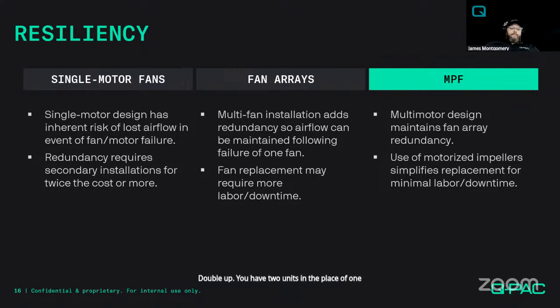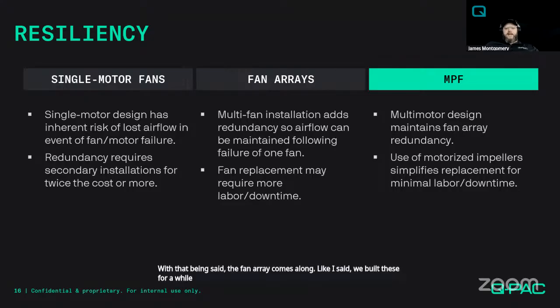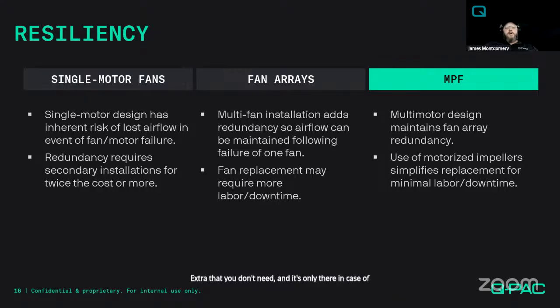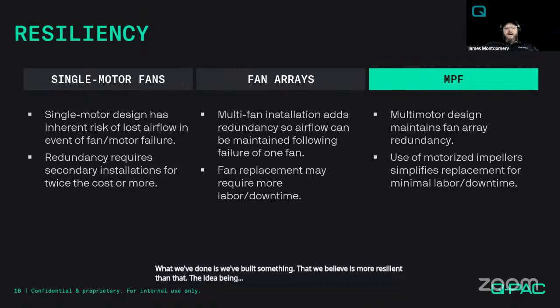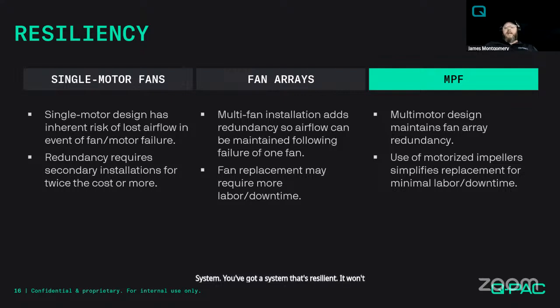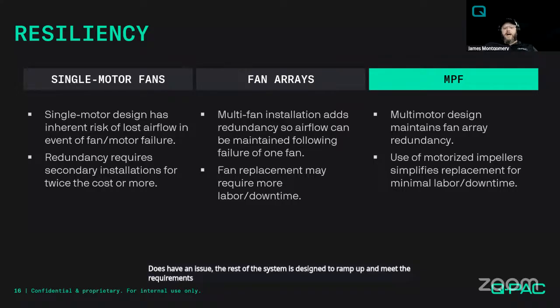And so with that being said, the fan array comes along. Like I said, we built these for a while. Multi-fans, it adds the redundancy. But redundancy implies extra that you don't need, and it's only there in case of emergency. What we've done is we've built something that we believe is more resilient than that. The idea being, instead of having a redundant system, you've got a system that's resilient. It won't fail. And if any individual component within it does have an issue, the rest of the system is designed to ramp up and meet the requirements, so you have zero downtime. So that's where I talk about the resiliency.